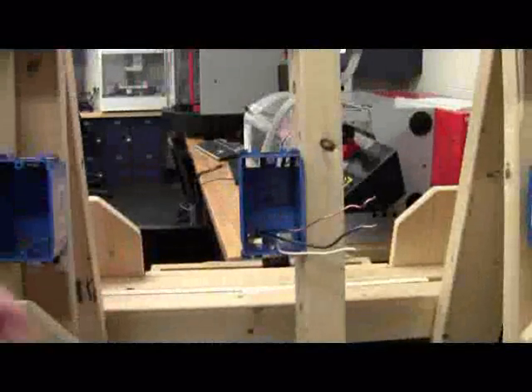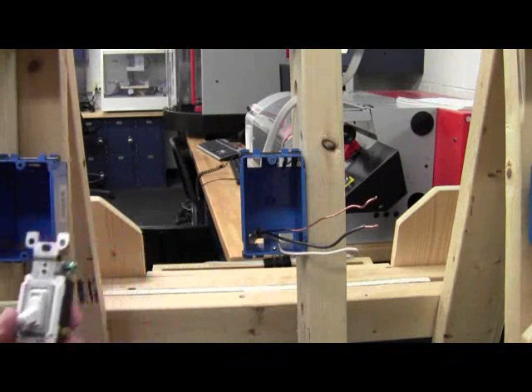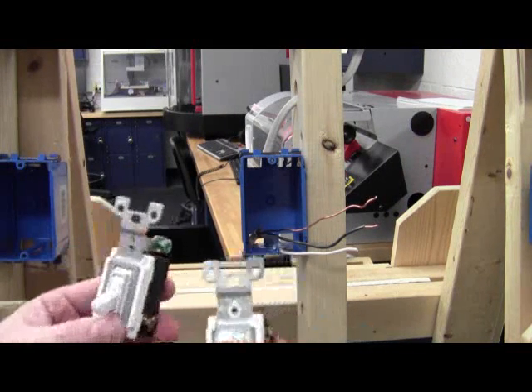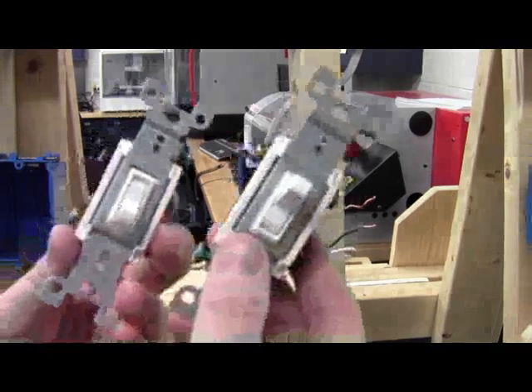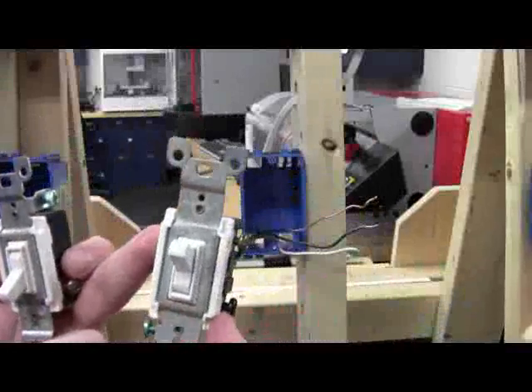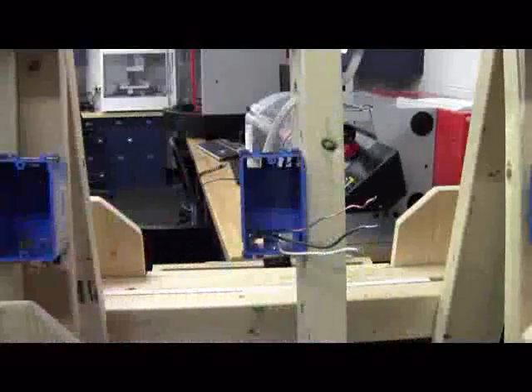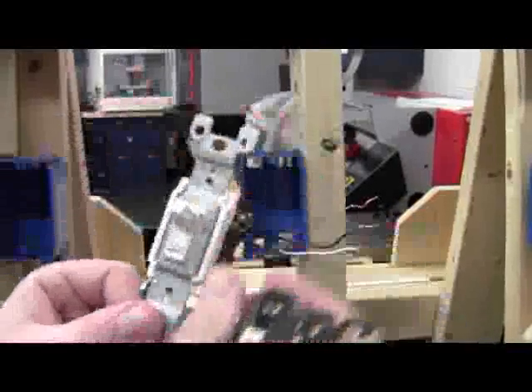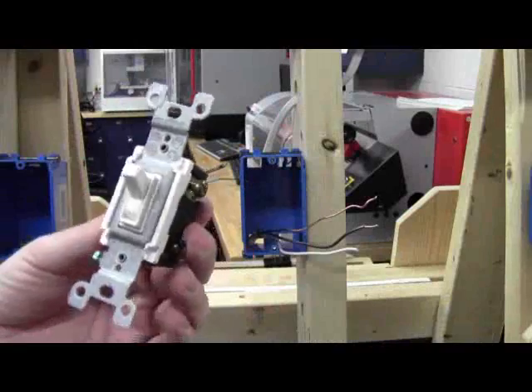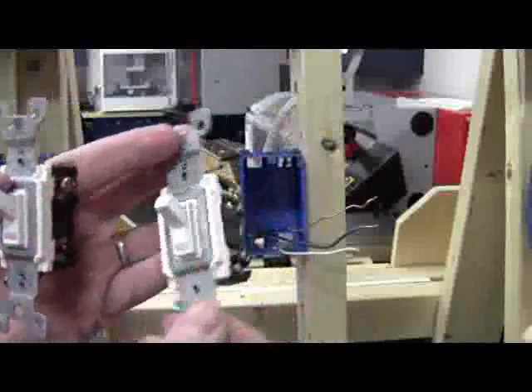It is worth mentioning that you have your switches oriented the correct way. It's a very common mistake for students to have it one way on one and this way on the other. So it's really important you look at your diagram and see that you have the two traveler terminals on the bottom, the single one on the top left, and that of course would not be like this, that would be like this. Now it can go either way, but it's just a lot easier to get it wired up if you're looking at it the same way as the diagram.